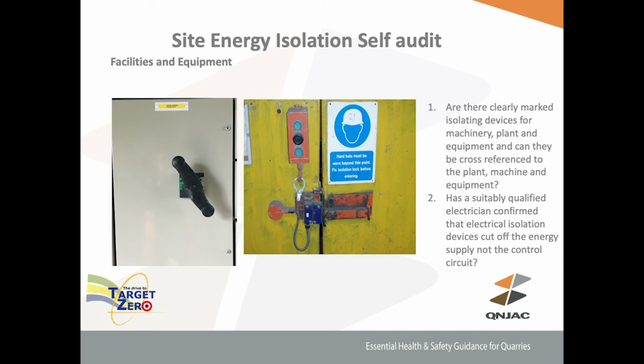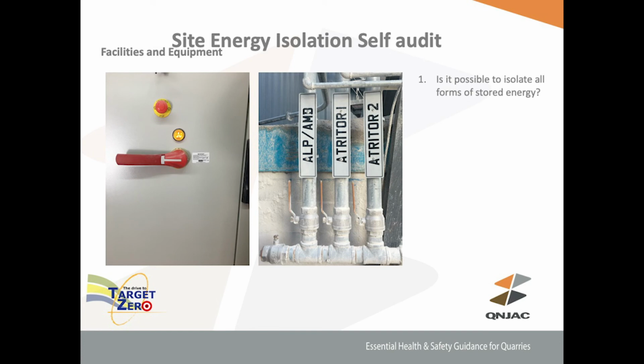You need to be very clear that before entering machinery, it is clearly isolated and the devices used clearly isolate the motive power and not the control circuit. These are the sort of things that need to be checked on the audit. That's one of the reasons we've sometimes not included trapped key systems in this, because people have sometimes used trapped key systems connected to control circuits, not physically connected to isolators, and used them for isolation of machinery.